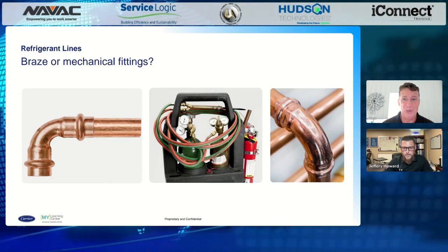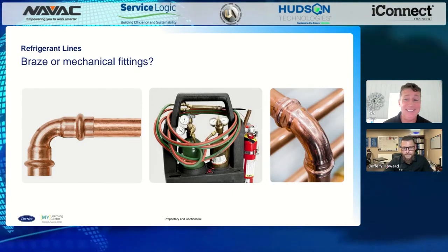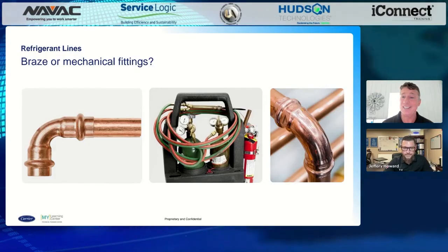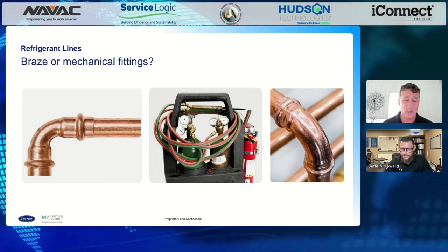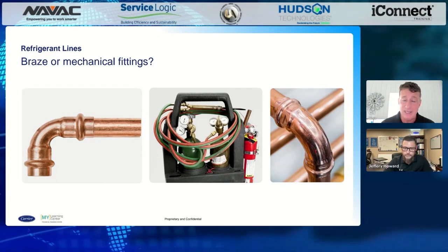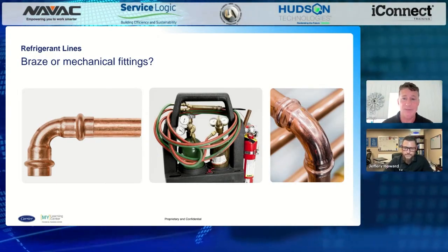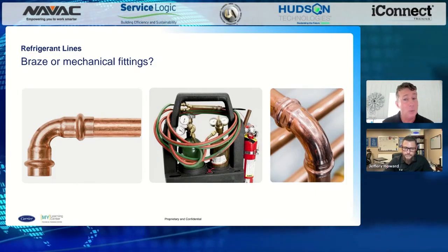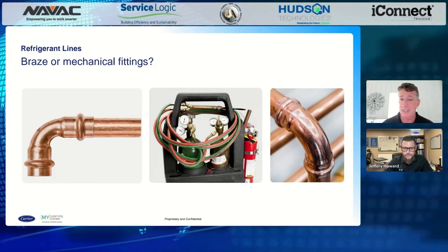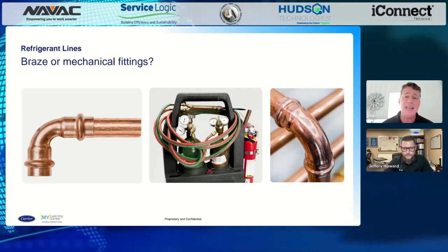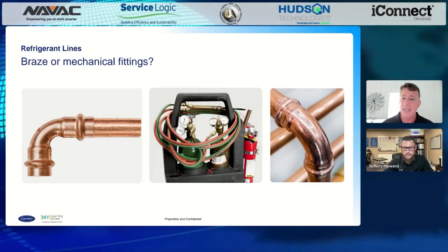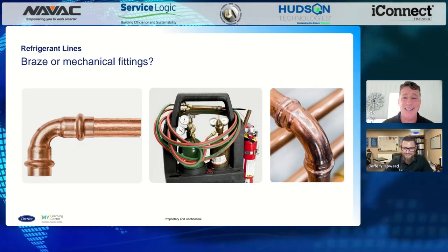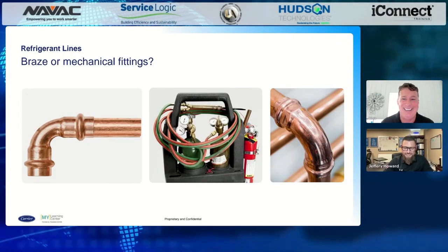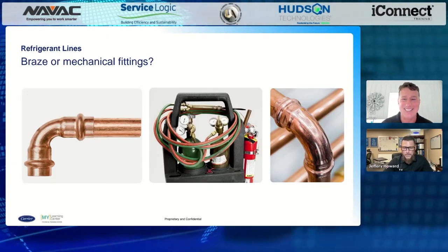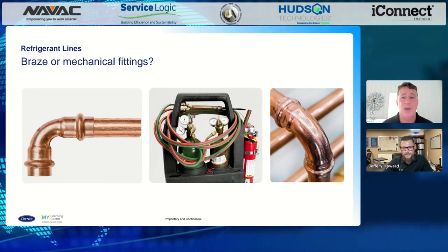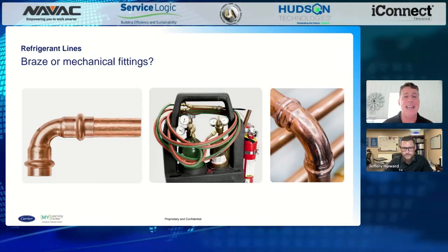You have to know the tool well, and it has to be cut and cleaned properly. If it's not done right, it's like any other process—if we miss one of those steps, it's going to be done wrong. Just like brazing, if I miss a step or forget a spot, I'm going to have leaks, and it's the same way with mechanical fittings. There was a period when a lot of manufacturers didn't allow mechanical fittings, but that culture is starting to change. It comes down to: are you not letting the refrigerant out? That's all we care about anyhow—are we creating a clean, sealed system? So I encourage you all to look at both options if you're not already working with both brazing and mechanical fittings.